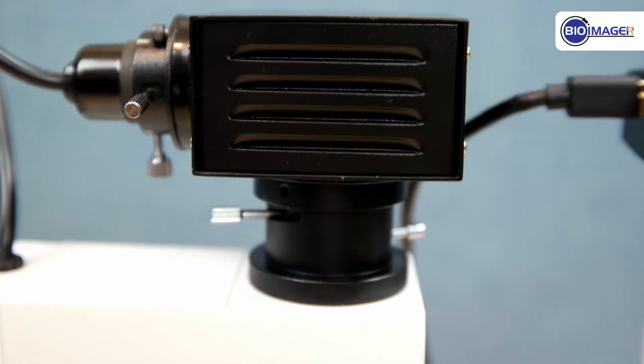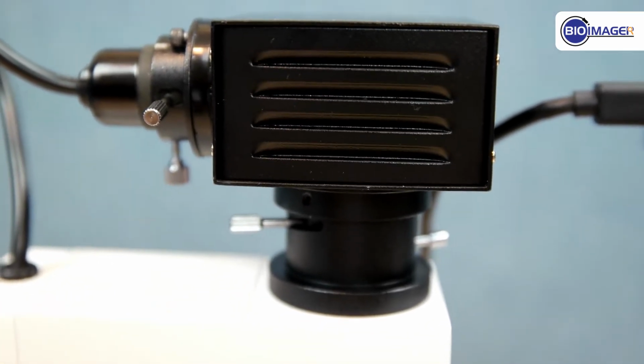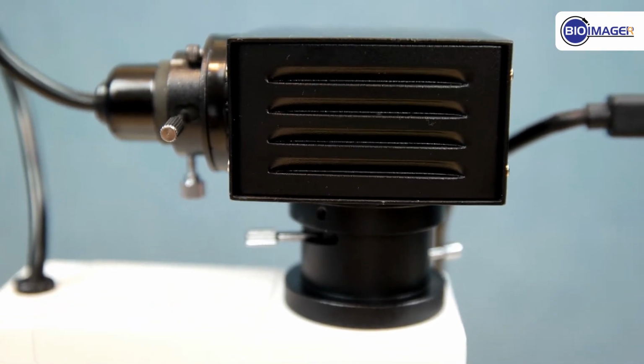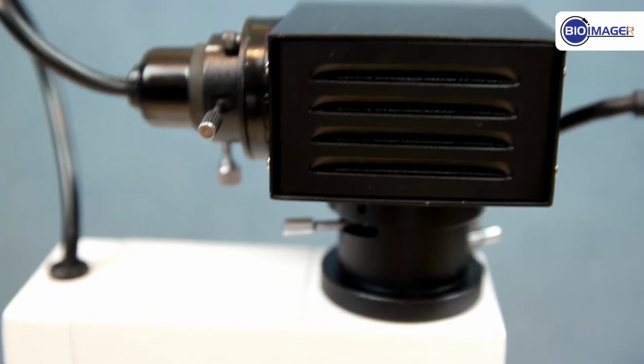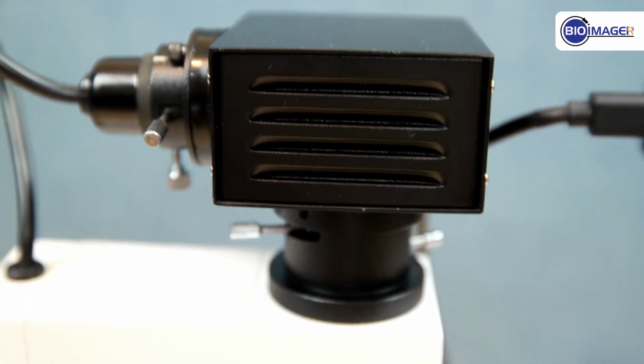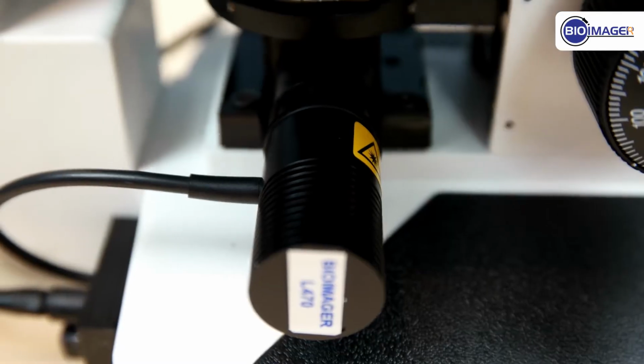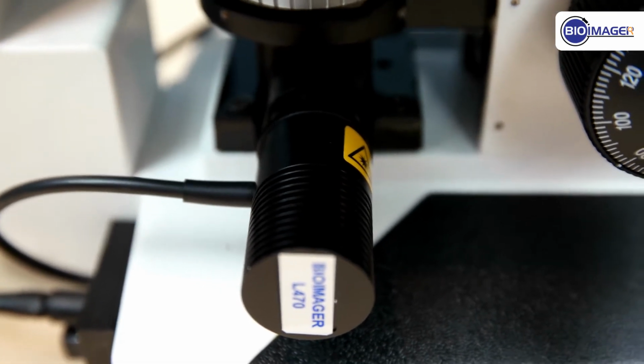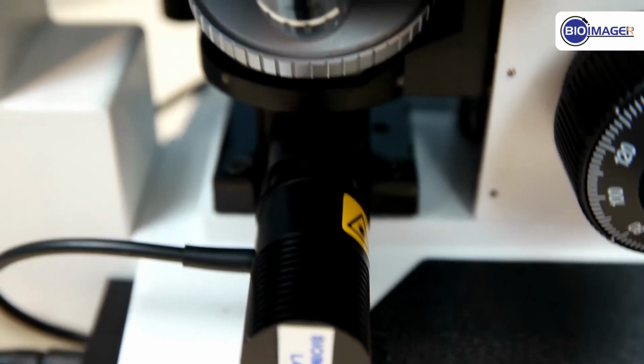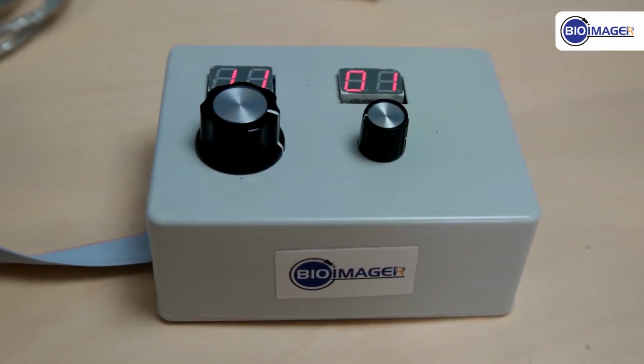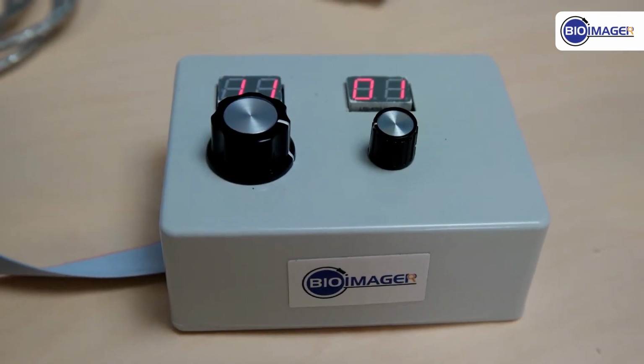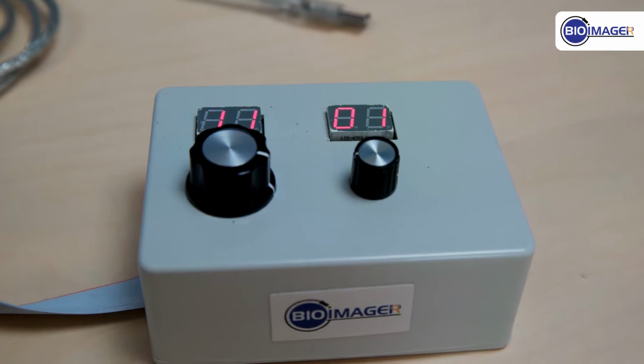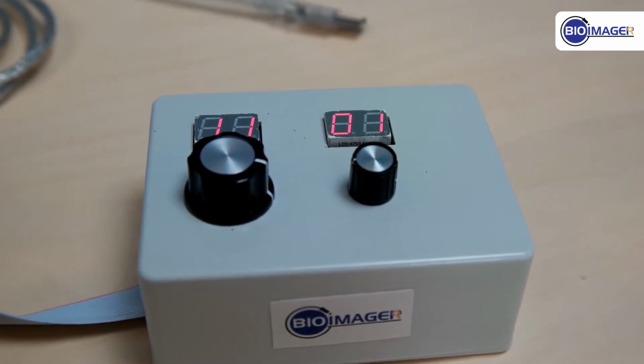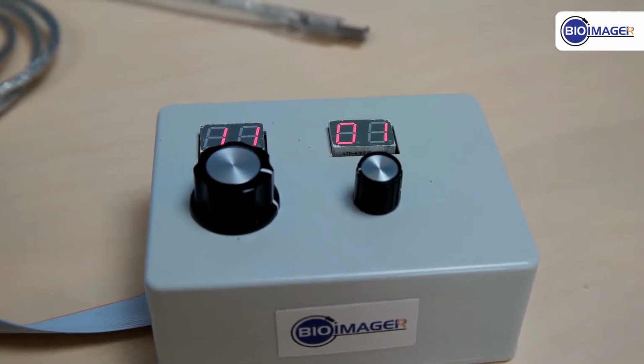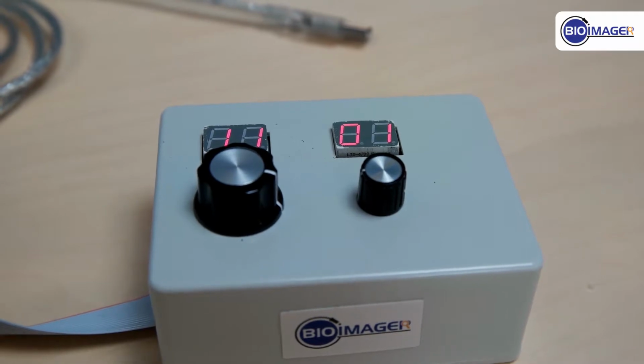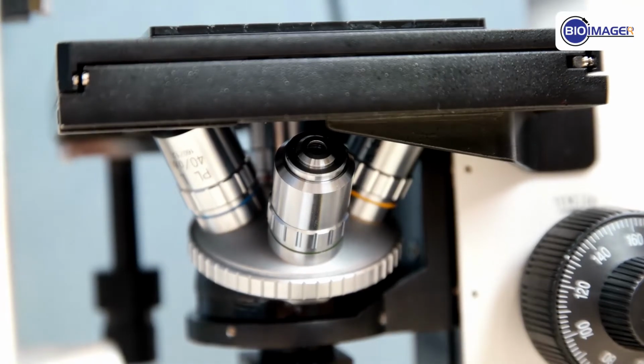This microscope uses LED as the light source for illumination. For bright field or phase contrast imaging, we use this lamp house at the top. For fluorescence imaging, we use another LED from the bottom. All of the LEDs are controlled using this manual controller. You can control the light intensity and also select the channel. All of these can be controlled from the software at the same time.